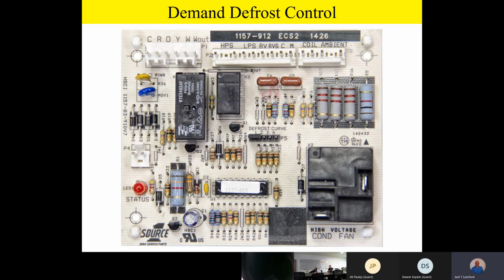So a time temperature control is different than a demand defrost control in the fact that it does the same functions as far as shutting the outdoor fan off and going into the air conditioning mode during defrost. That all stays the same. However, how it gets to defrost is different. So a time temperature control has a simple Klixon switch, or a temperature switch, mounted on the lower coil pass of the outdoor coil. And the defrost control is just sitting there monitoring that switch.